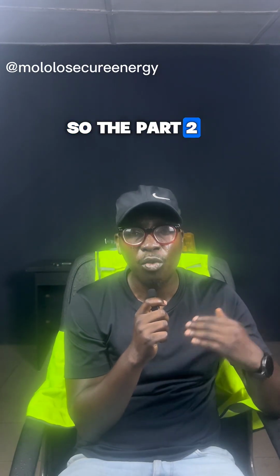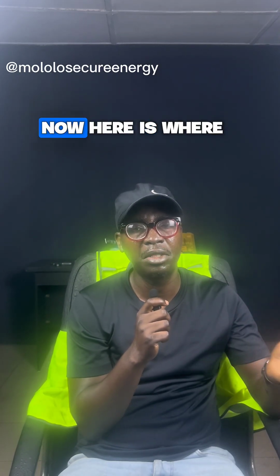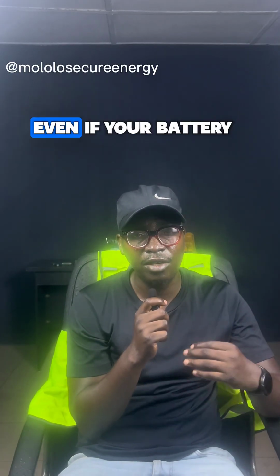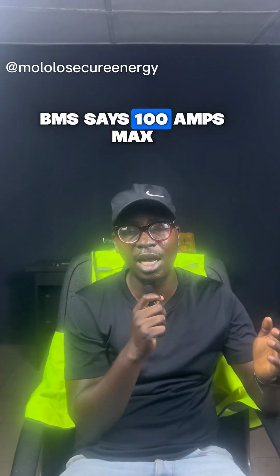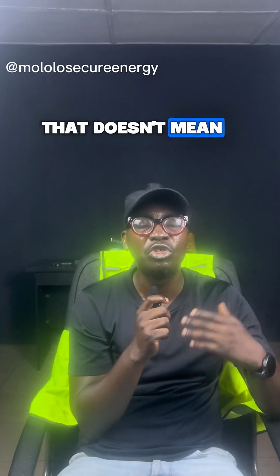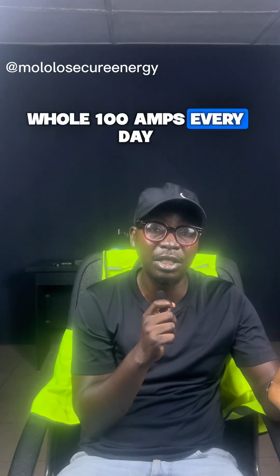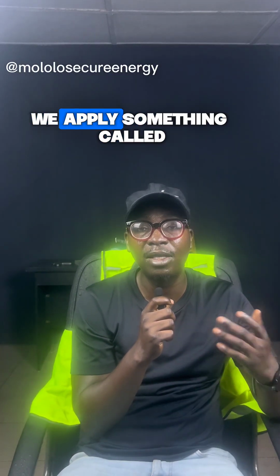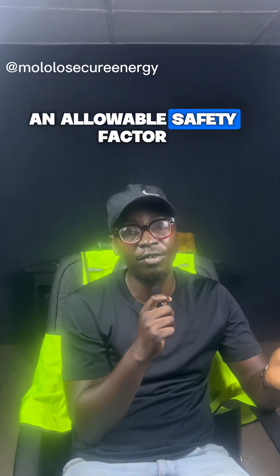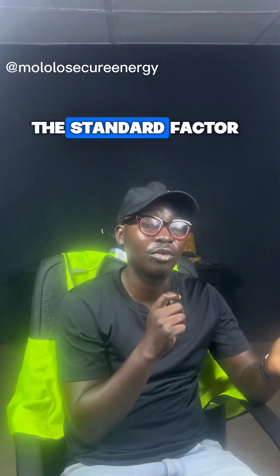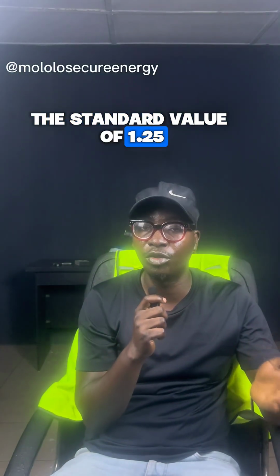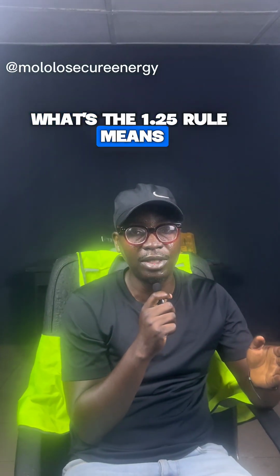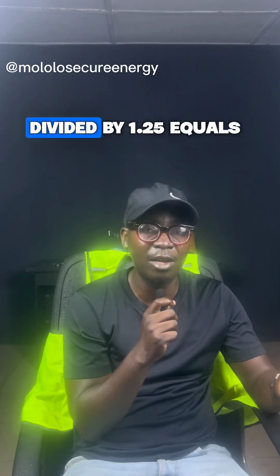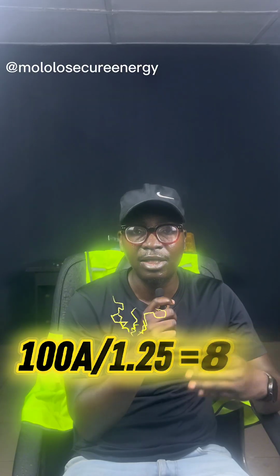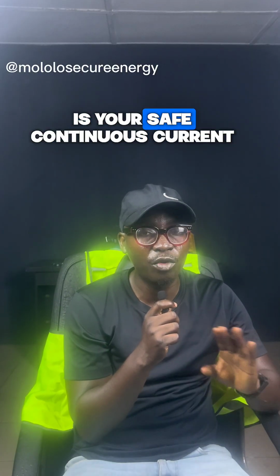So the part two, where the safety rule comes in. Now, here is where professionals separate themselves. Even if your battery BMS says 100 amps max, that does not mean you should use the whole 100 amps every day. In electrical design, we apply something called an allowable safety factor, which we call the standard factor, the standard value of 1.25. What the 1.25 rule means in plain English, you divide the maximum rating by 1.25. So your 100 amps divided by 1.25 equals 80 amps. This means 80 amps is your safe continuous current.